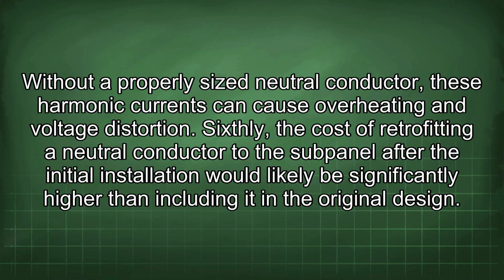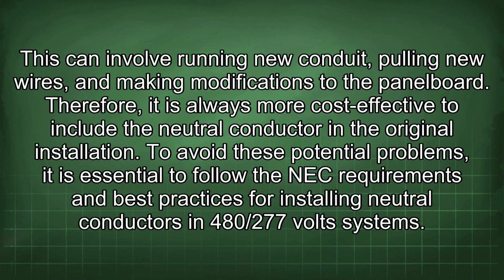Sixthly, the cost of retrofitting a neutral conductor to the sub-panel after the initial installation would likely be significantly higher than including it in the original design. This can involve running new conduit, pulling new wires, and making modifications to the panel board. Therefore, it is always more cost-effective to include the neutral conductor in the original installation.